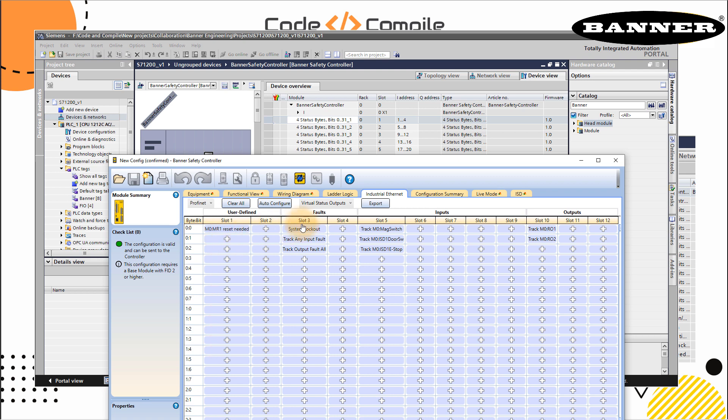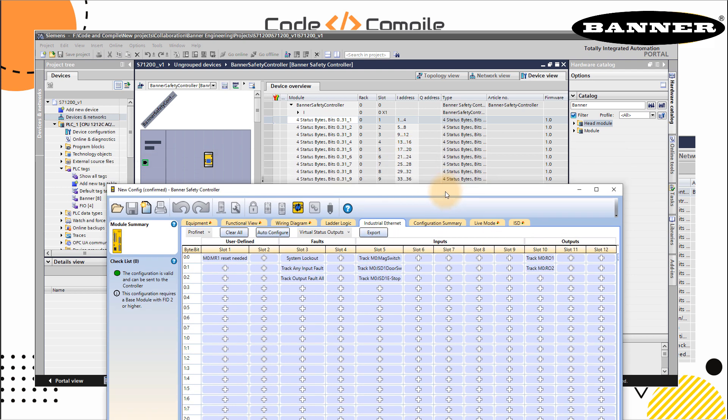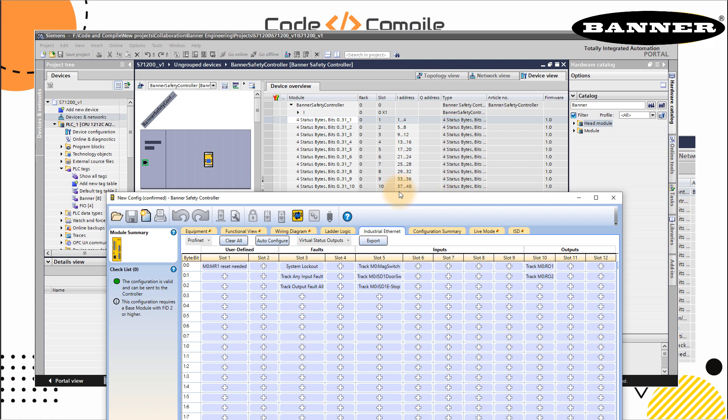Similarly, for slot three, you can see here slot three is here. The address is starting from I9. So the first address of this slot is I9.0, and I9.1, 9.2. Similarly, for the magnetic switch is slot five, which is I17. So I17.0, .1, .2. And similarly, for slot 10, you have I37.0 and .1.